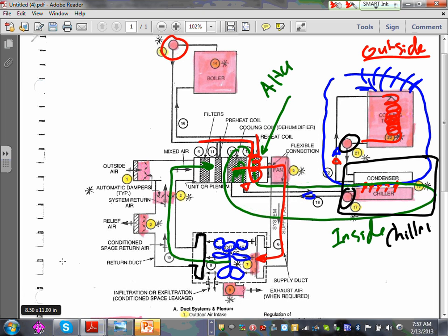How do they make it hot or how do they make it cold? Very simple. They have a coil that's connected to the boiler that will bring you the heat, and a coil that's connected to two pipes that are connected to the chiller, and that's how they get the chilled water or the cool. Any comments, any questions? So that's how your system is put together.